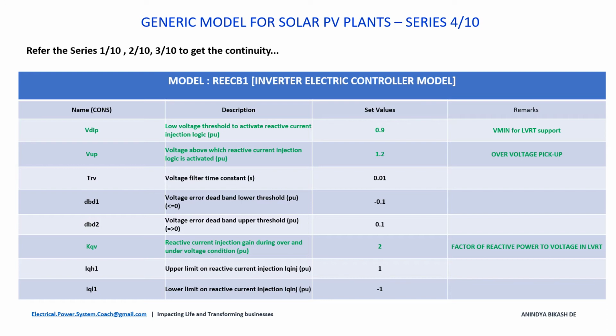So other parameters you can see, that is voltage filter time constant, voltage error deadband for lower threshold and upper threshold. Those are default parameters. And the next important parameter is the KQV, reactive current injection gain during over and under voltage condition. So basically this KQV has different ranges. It varies from 0, 1, 2, 3 and 4.